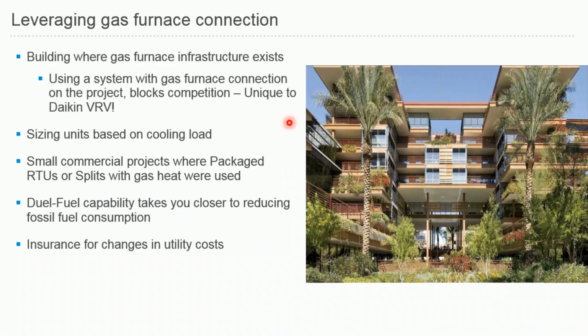Also, this will allow you to reduce your system size in certain cases. Because especially in colder climates, when you size your system based on heating loads, the chances are that you will be oversizing your equipment when it comes to cooling. So if you go with the gas furnace heating option, in this case, you'll be able to reduce your system size because you'll be sizing your unit based on the cooling loads. That's another thing that you can utilize.